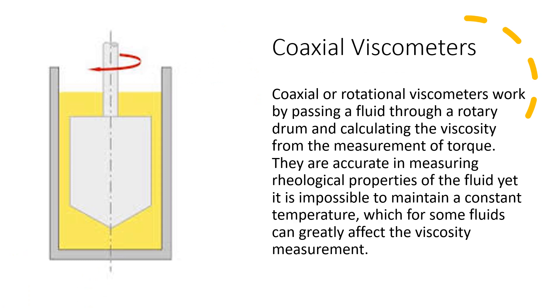Next, we're going to look at coaxial viscometers, which are rotational viscometers. They work by passing a fluid through a rotary drum and calculating the viscosity from the measurement of the torque. They're accurate in measuring rheological properties of the fluid, yet it's impossible to maintain a constant temperature, which can greatly affect the viscosity measurement, since some fluids are highly viscous at low temperatures and low in viscosity at high temperatures.